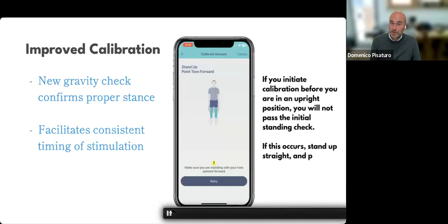The first one is what we call the gravity check. During the first step of the calibration, when you're asked to stand up, the system will now verify that you're actually standing up. If you're not standing up during that measurement, you will not pass the calibration step, and you will have to repeat.